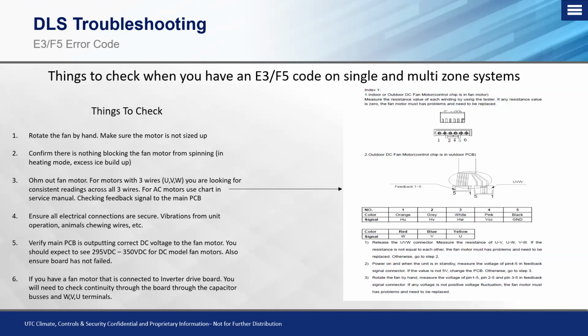If you're getting wacky readings on one of the legs, chances are you might have an issue with that coil in the fan motor, and when it goes to start up, and I talked about that pre-pulse or that rotational reference, that could be your issue right there and why you're coding out on this E3 F5 code. Now, if you're dealing with an older style AC fan motor, and they're typically known by the 5 wires that go to the fan motor, you want to make sure that you use the chart in the service manual, checking feedback signal to that main PCB.